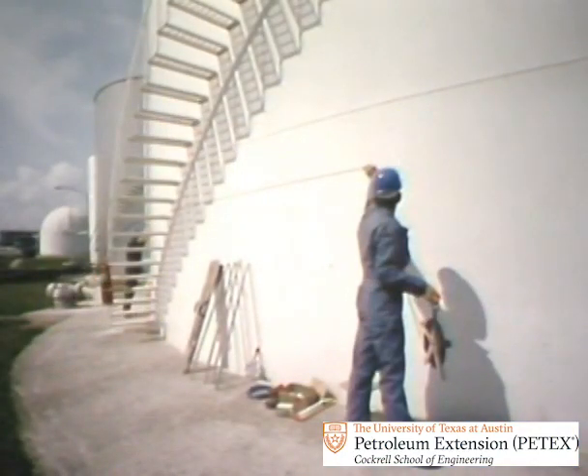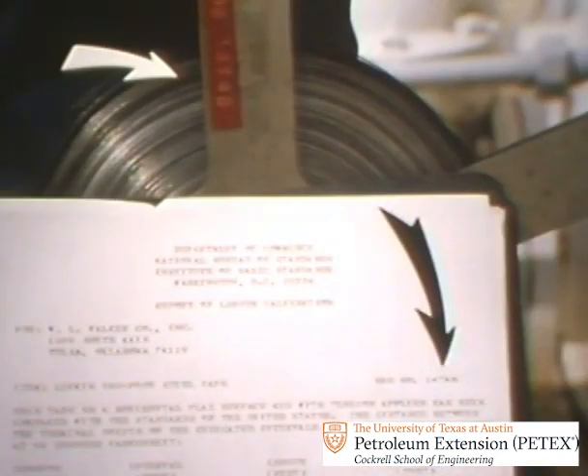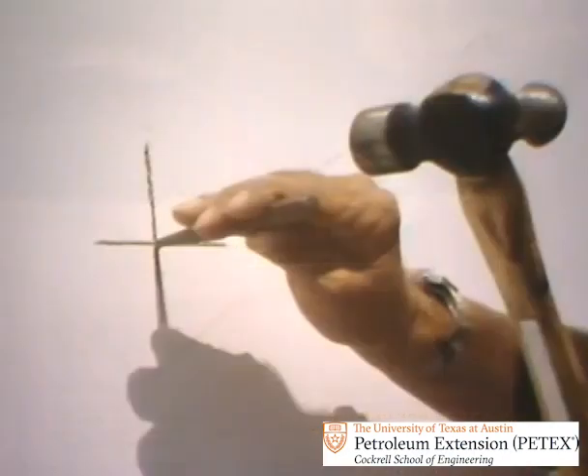Now let's watch a crew measure the bottom ring circumference with the standard tape. First, they check the number embossed on the standard tape to be sure it matches the number on the NBS report. They want the right tape with the right report. Then a crewman lightly center punches the shell on the marked tape path. This small indentation establishes an anchor point for holding the standard tape.